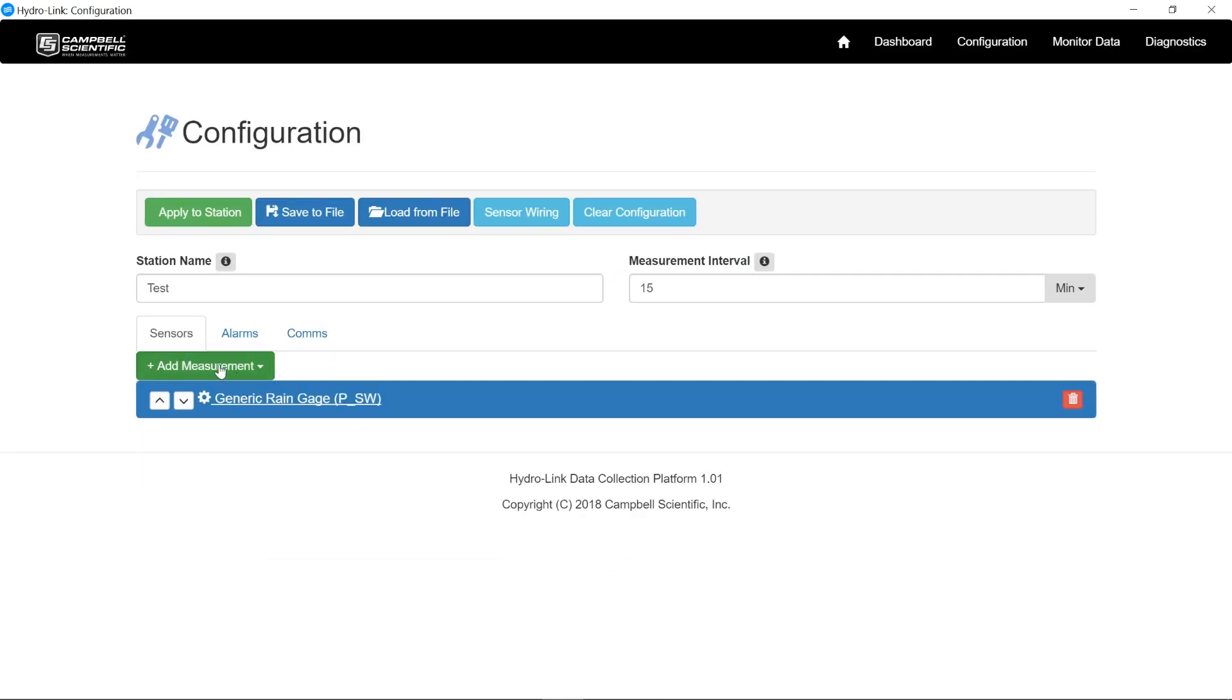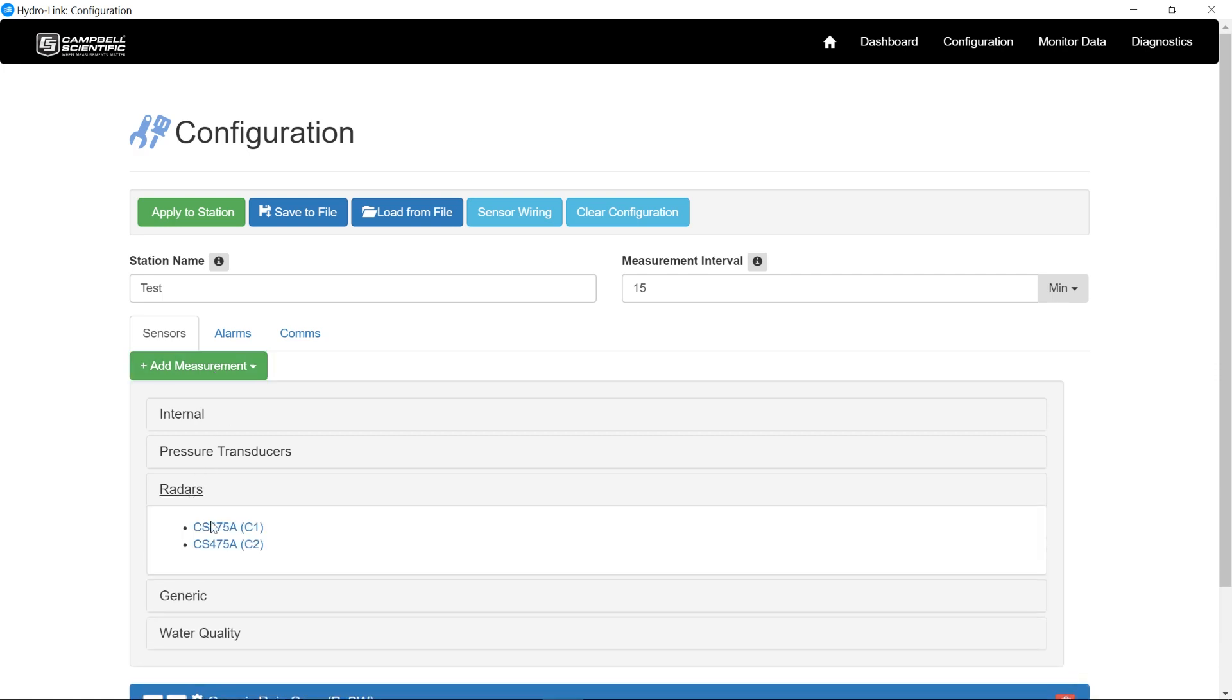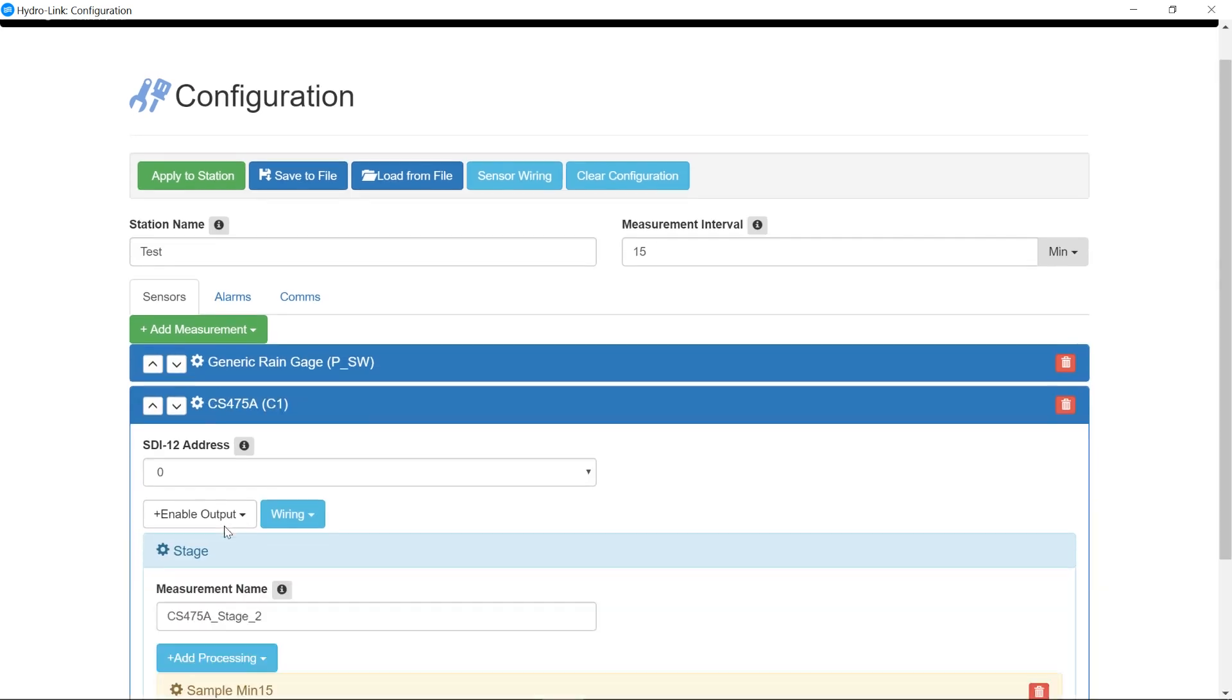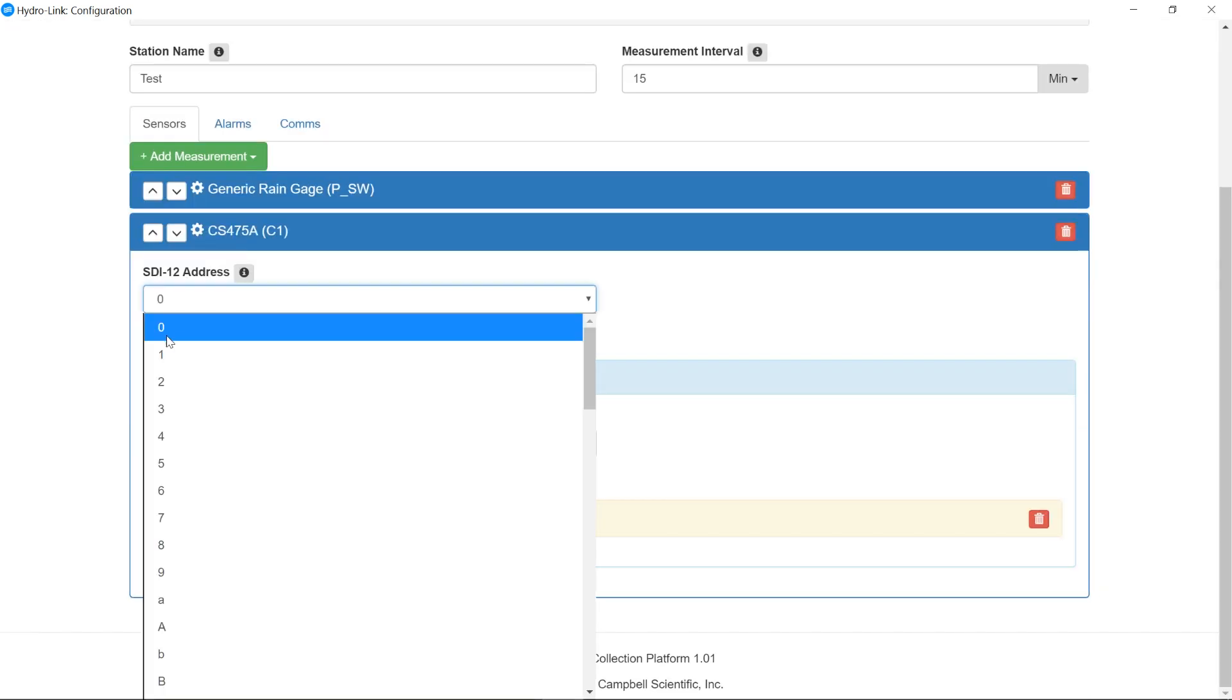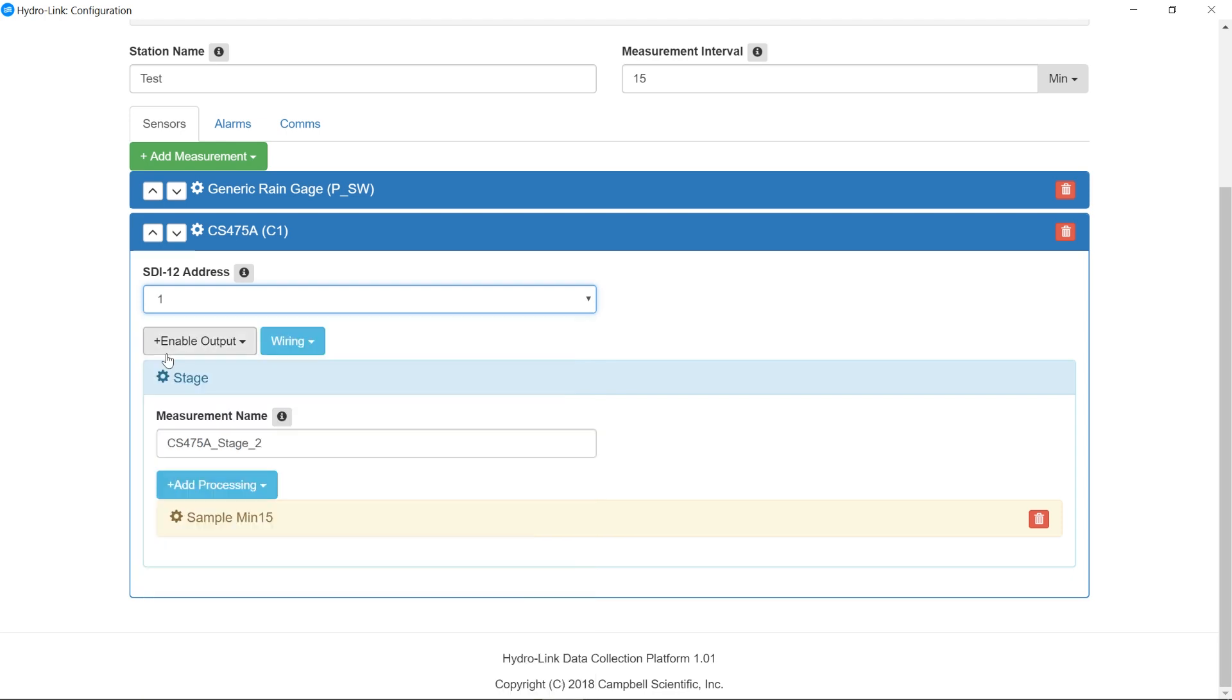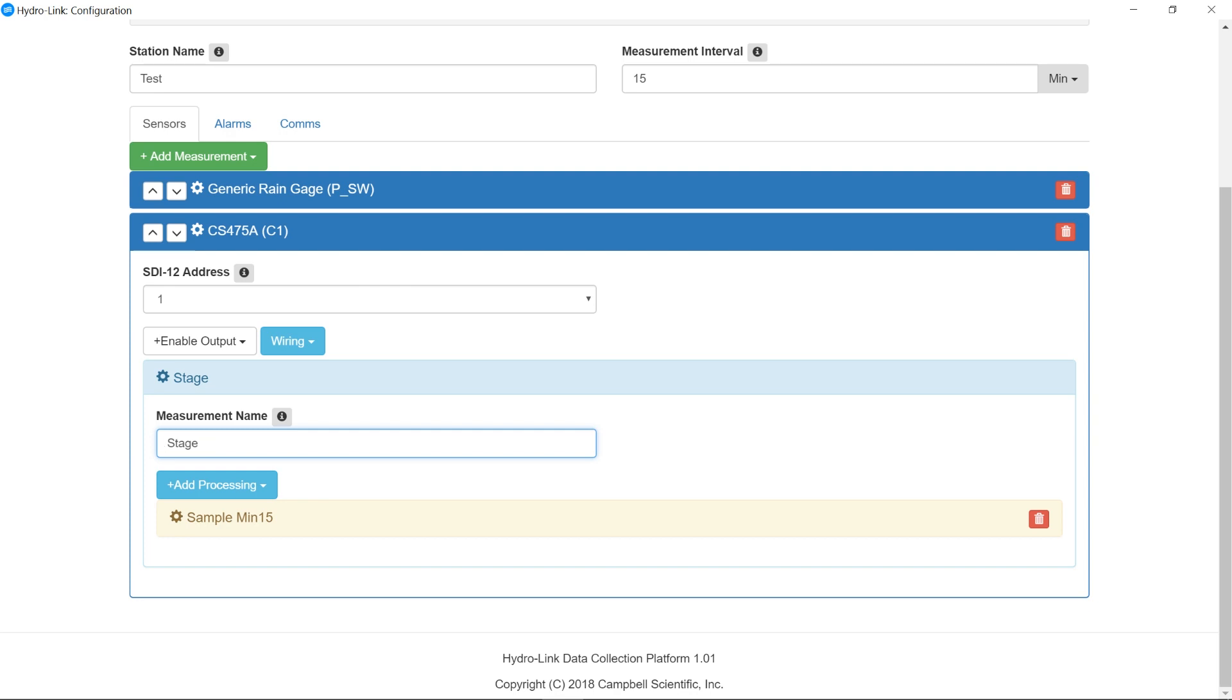I can click on the name and shrink it down, minimize it. I also want to add in a water level sensor. I'm going to add in a radar sensor. I'm going to add in a 475 on control port 1. Control port 1 and control port 2 can be used for SDI 12 and they're independent of each other. So I'm going to click on that. It comes up and it gives me the address. I'm going to change this to address one measurement. I'm going to change this to simply just be stage.